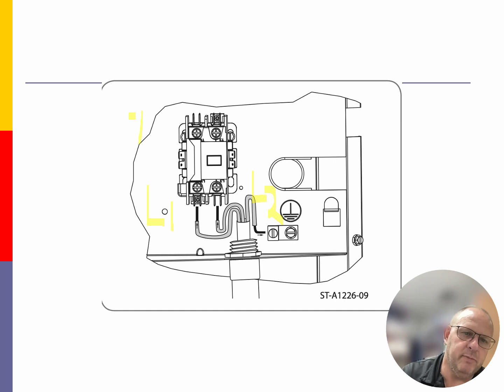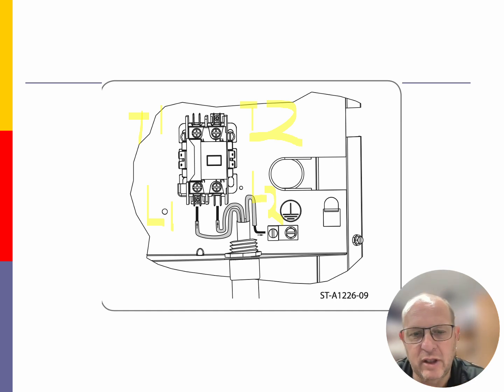Now, I'm going to bring the line voltage into the line side of the contactor. The line side of the contactor may have a couple of wires hooked onto it, depending on what the schematic drawing is trying to tell us. But for the most part, I'm going to have these two wires here. They're probably going to be color coded out in the field. We'll use black and white, but for the most part, the NEC is our standard for this. So we'll be doing black on one side of the unit, and then the other color for this side will be a red color, and that's just indicating that it is a 240 circuit.